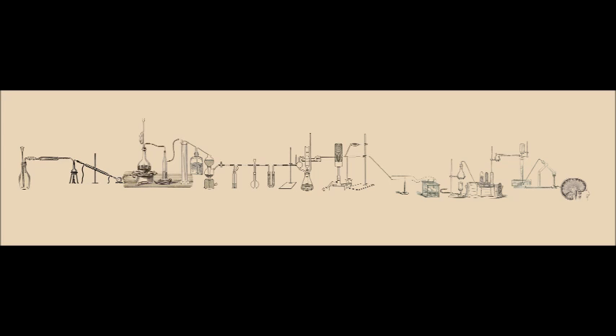Rinse the probe with deionized water and blow dry with tissue. Place it in the buffer of pH 7. When it stabilizes and the graph icon appears, press the Cal button again. Make sure it reads Cal OK before taking the probe out and rinsing again. Repeat this but in the buffer of pH 4. The probe is now calibrated and you can then place the probe back in the bottled solution for the time being.